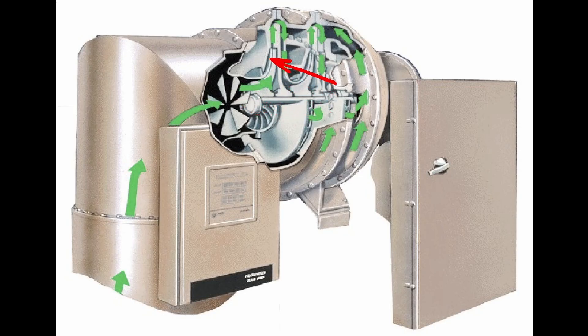We're going to pass through this first stage up into our diffuser. This diffuser is going to feed directly into the second stage. Then this second stage, depending on if we have a CVH-E or CVH-F, will be a fixed or variable guide vane.